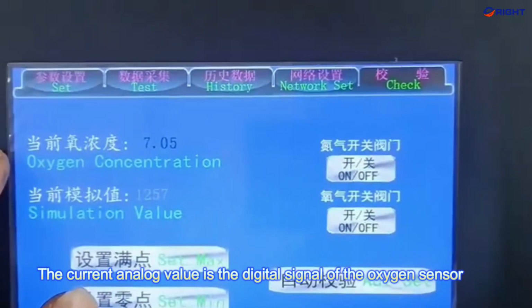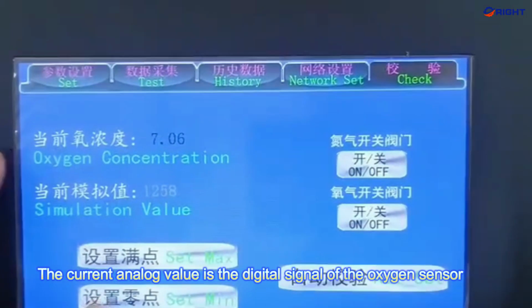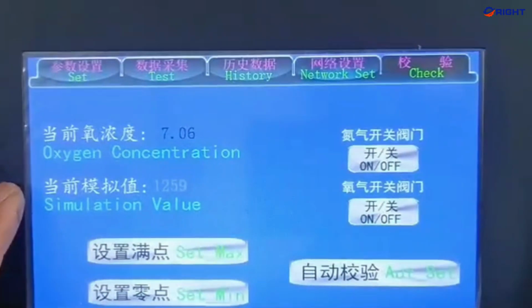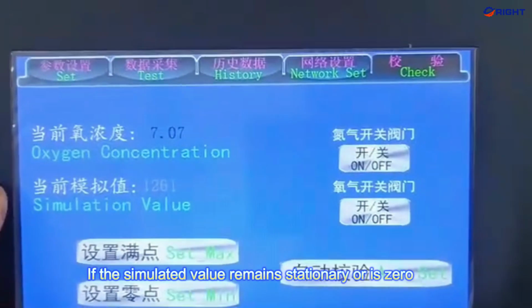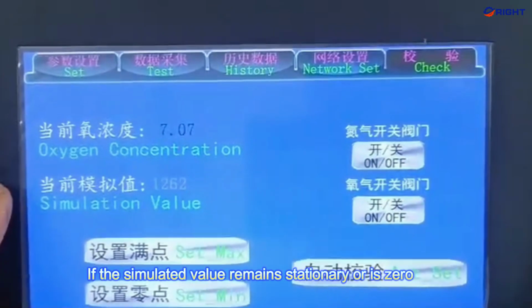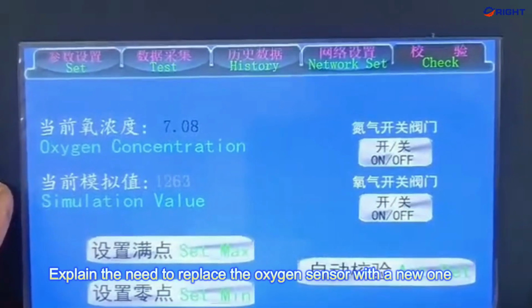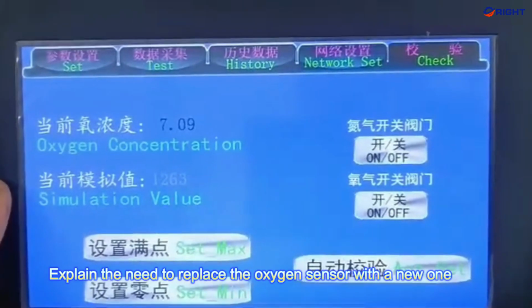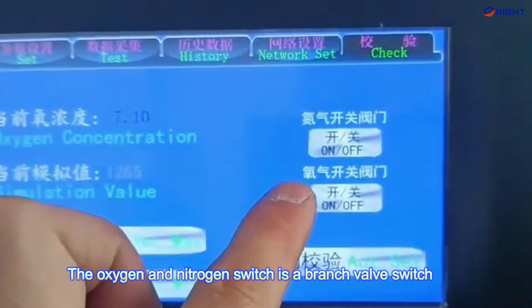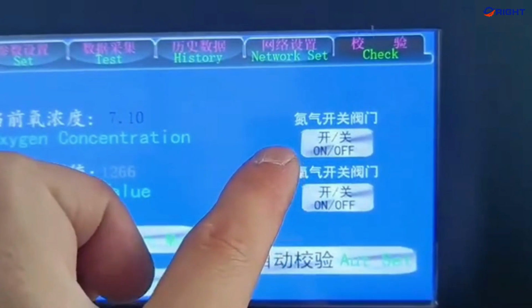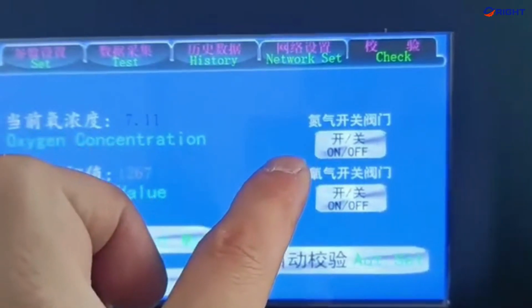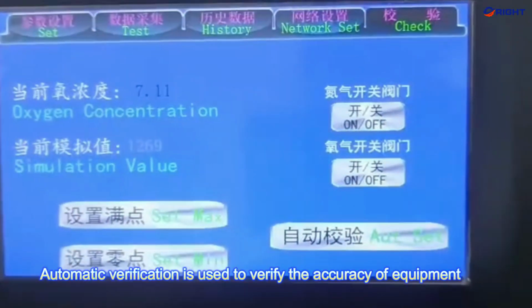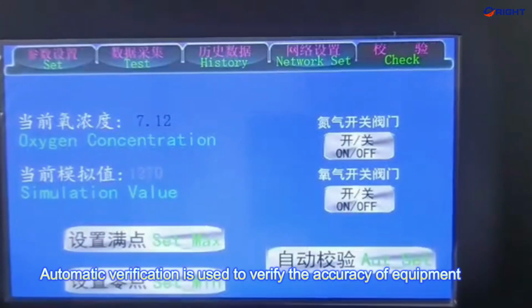The current analog value is the digital signal of the oxygen sensor in the state of pure oxygen supply. If the simulated value remains stationary or is zero, it means the oxygen sensor needs to be replaced with a new one. The oxygen and nitrogen switch is a branch valve switch. Automatic verification is used to verify the accuracy of the equipment.